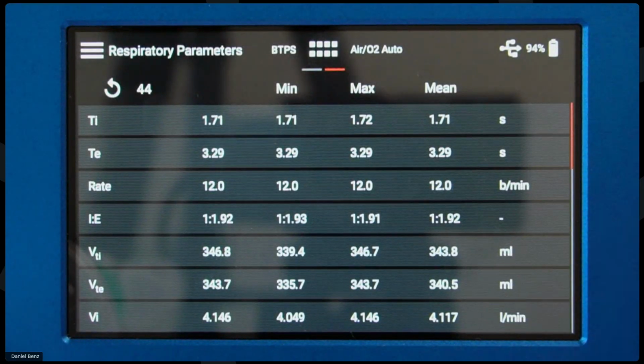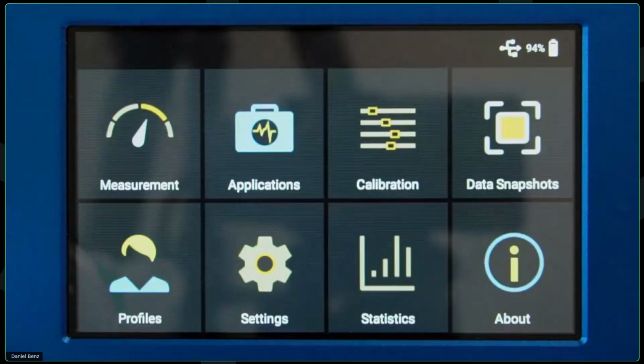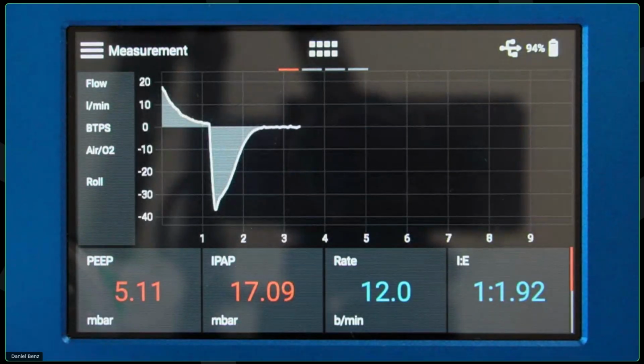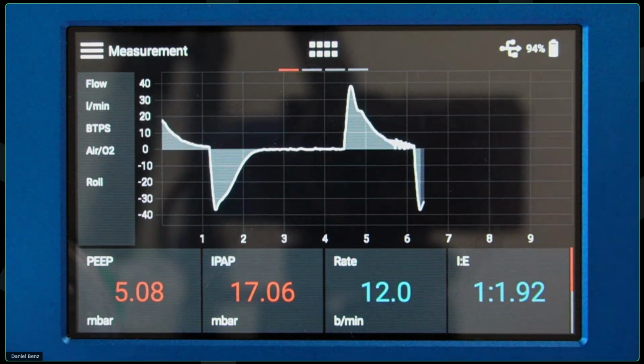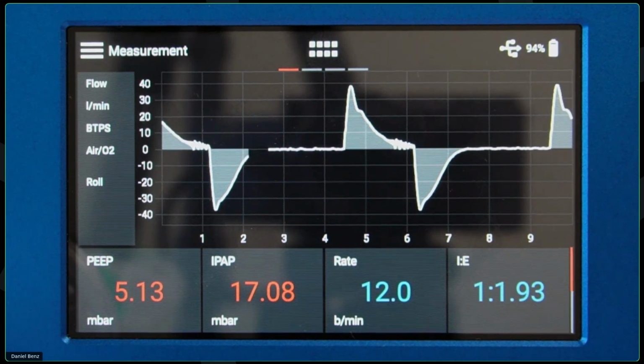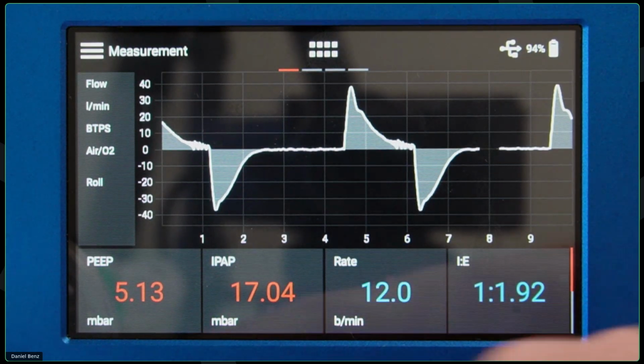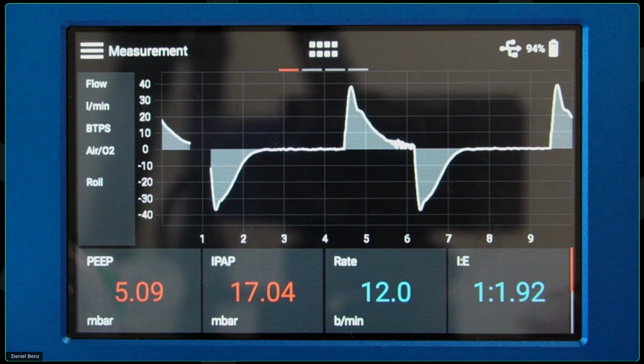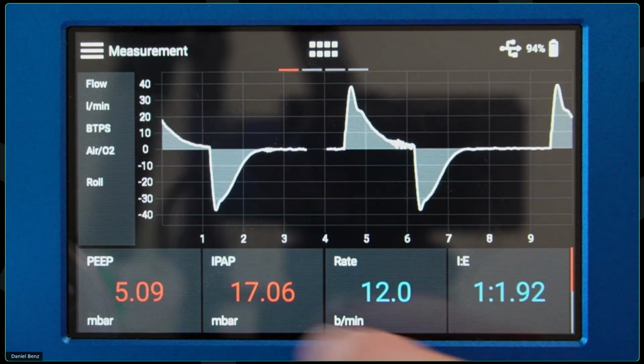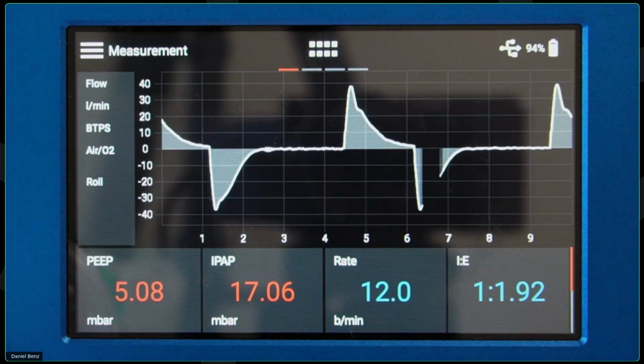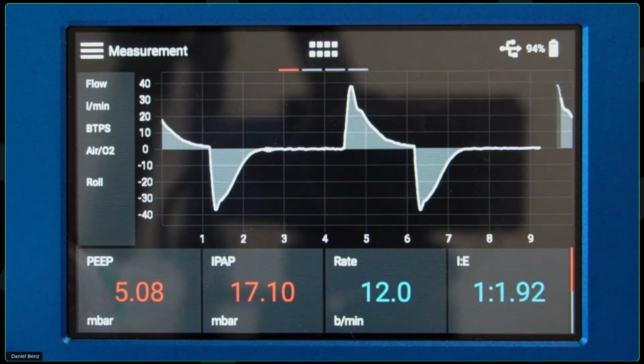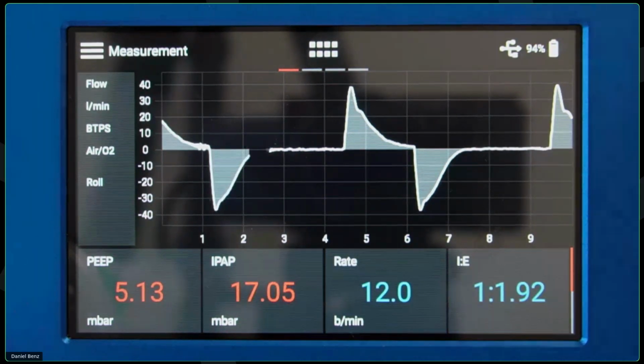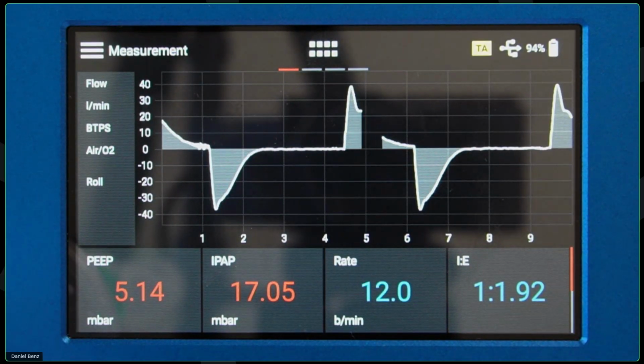Right now, in my current application with my Bella Vista ventilator I've connected here, you can see that with each inspiration, I have a positive flow through my FlowAnalyser, and with each exhalation, I have a negative flow through my FlowAnalyser. This is very typical in ventilator testing, and as you can see, the default trigger settings work well. I can measure all my parameters here. My ventilator is set to 12 breaths per minute, so that's good. My PEEP is 5, and this is all looking good. And you can see up here in the screen, there is a small TA flashing up with each start of a new breath cycle. So this indicates that the FlowAnalyser is able to trigger.